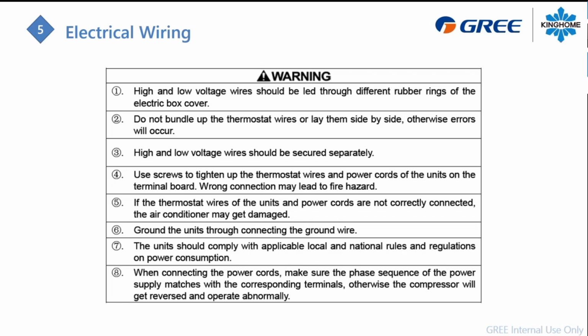Make sure you have a proper ground too, from your furnace and from the outdoor unit. The ground is really important. We have a lot of communication inside of the unit. You don't send communication to the outdoor unit, but inside of it there's a lot of communication, because the compressor is inverter. It will be driven from a kind of back and forth communication. So you need a proper ground to make it work correctly. And always use your local and national rules about the power and the connection.